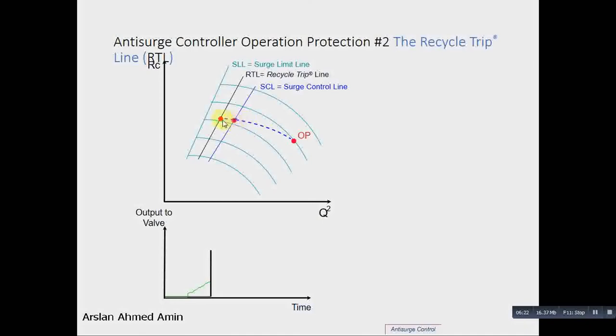When your operating point touches this recycle trip line, a quick response is generated, and this magnitude is equal to the derivative of this rate of change. Therefore, the total response is the sum of this PI response plus this recycle trip response. And therefore, the operating point returns back to the surge control line.